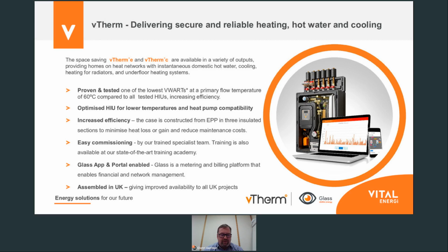So at Vital, we've taken a slightly different view. We've gone back to basics with our heat interface units and looked at how we can optimize those systems to operate at lower temperatures. This means we've gone back to look at the plate designs, increasing the plate sizes and the flow rates through our heating plates. We've also looked at the casing of the system to make sure heat losses are the best they possibly can be, and at the internal pipework diameter in the HIU to optimize the flow rate through the units, ensuring we get the best performance and efficiency out of the heat interface unit.